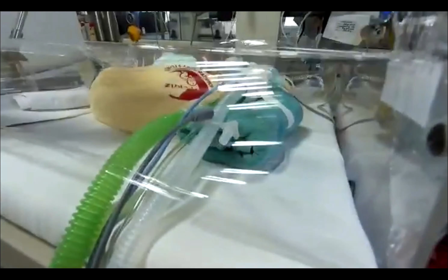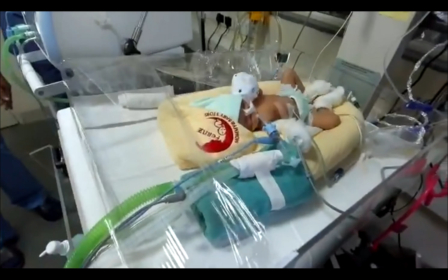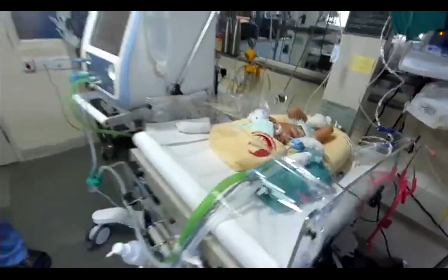So it is the sensing probe. If it is sensing the heat from the radiant warmer, it will not correctly give us the assessment of the airway temperature. So we need to tell the maintenance people to correct the room temperature. Yes. And there is some water in the water trap which we need to clean. So, Sister Ankita, how is the supportive care assessment?